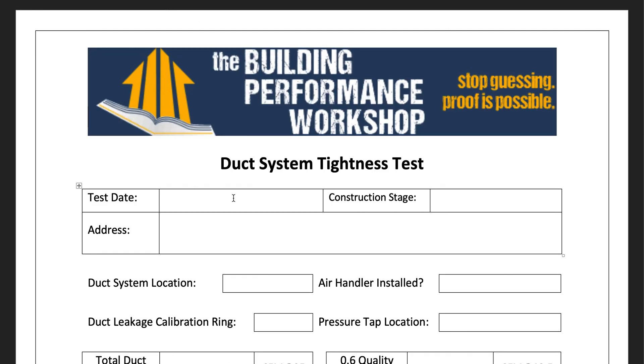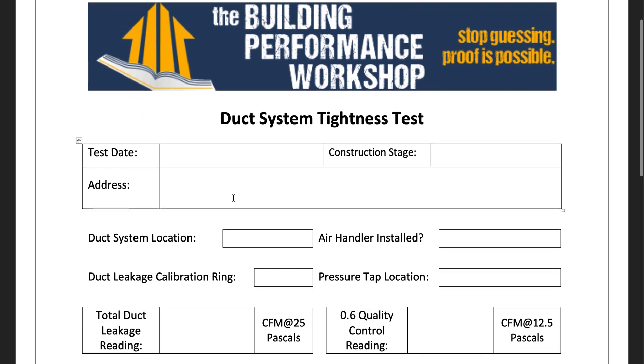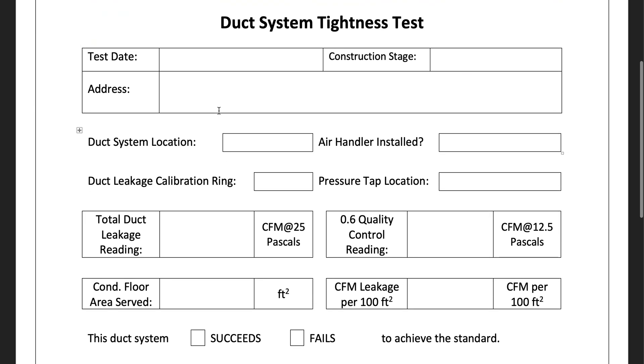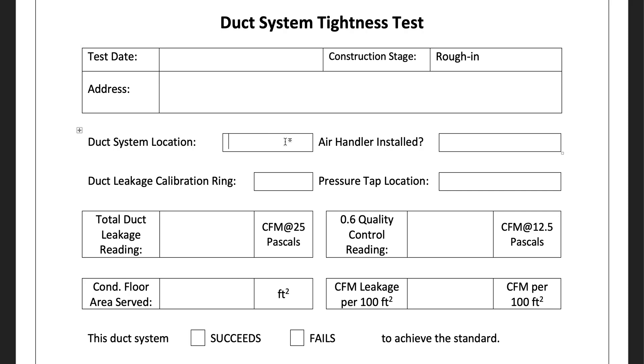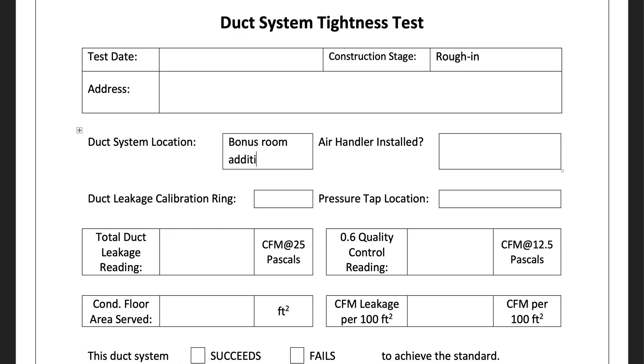The duct system tightness test is the other report template you can download from the same page at our website. Again: date, construction stage — really important. Rough-in is the time to do this, period. If you're coming in at final, you want to show that on your report for sure. The location — let's say it's a bonus room addition. Air handler installed: yes or no. If it's yes, then you have a different leakage level that you're allowed to hit.